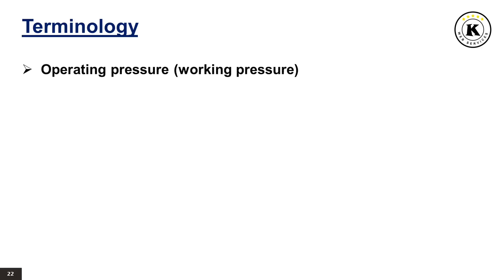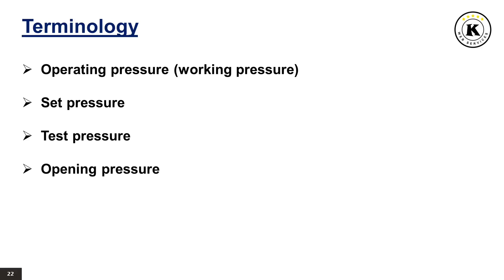Operating pressure or working pressure is the gauge pressure existing at normal operating conditions within the system to be protected. Set pressure is the gauge pressure at which, under operating conditions, direct loaded safety valves commence to lift. Test pressure is the gauge pressure at which, under test stand conditions or atmospheric back pressure, direct loaded safety valves commence to lift. Opening pressure is the gauge pressure at which the lift is sufficient to discharge the predetermined flowing capacity; it is equal to the set pressure plus opening pressure difference. Reseating pressure is the gauge pressure at which the direct loaded safety valve is reclosed.